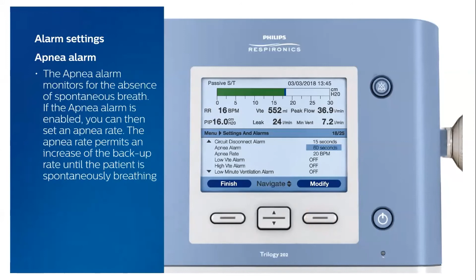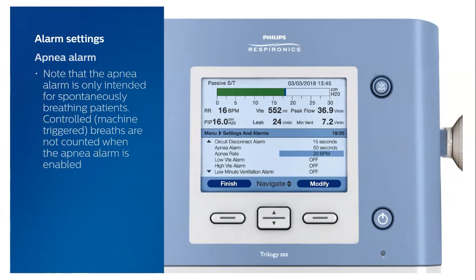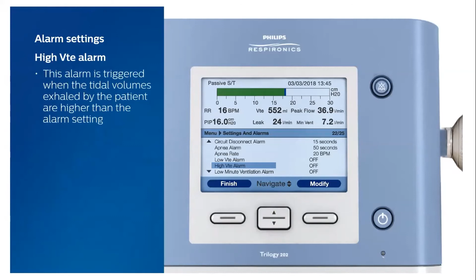The apnea alarm monitors for the absence of spontaneous breath. If the apnea alarm is enabled, you can then set an apnea rate. The apnea rate permits an increase of the backup rate until the patient is spontaneously breathing. Note that the apnea alarm is only intended for spontaneously breathing patients. Controlled, machine-triggered breaths are not counted when the apnea alarm is enabled. Low VTE alarm. This alarm is triggered when the tidal volumes exhaled by the patients are less than the alarm setting. Enabling this alarm in AVAPS will cause the alarm to be triggered only after the device has reached the maximum IPAP pressure setting. High VTE alarm. This alarm is triggered when the tidal volumes exhaled by the patient are higher than the alarm setting. Low minute ventilation alarm.